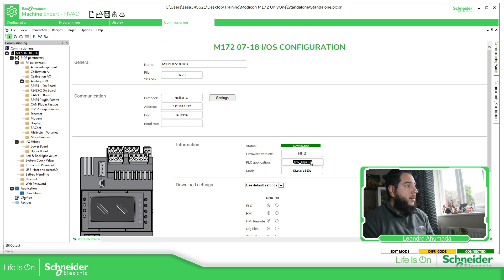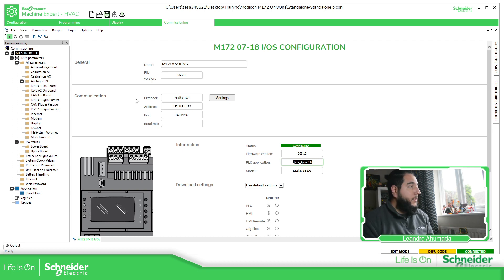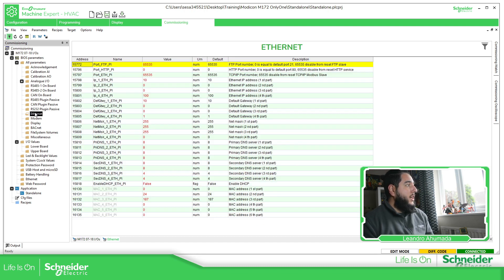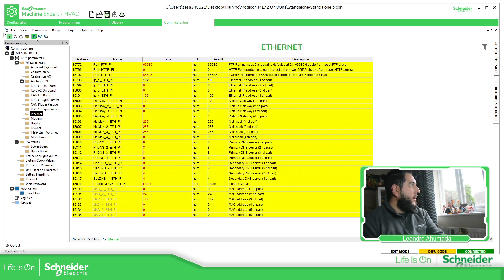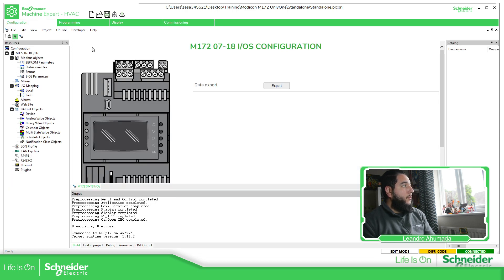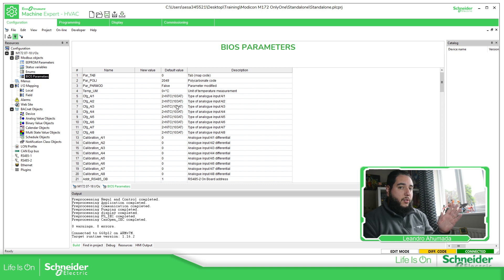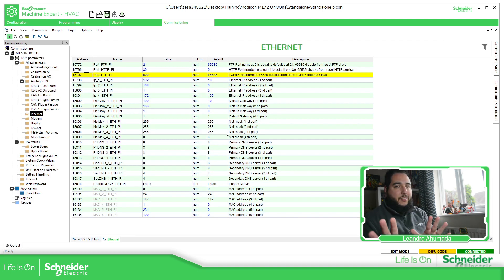As you can see, I am now connected with the controller. The PLC application has a different name compared to the one I have in the software. At the bottom you can see the status showing I'm connected, but the code is different. Now I can read information from the controller. For example, to check the IP address, I can select that parameter and press Read, or I can use the Select All button to select all parameters and then read them all. The column 'Just Value' shows the actual value read from the controller.